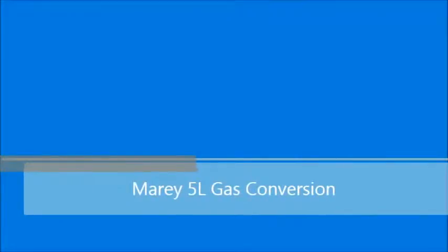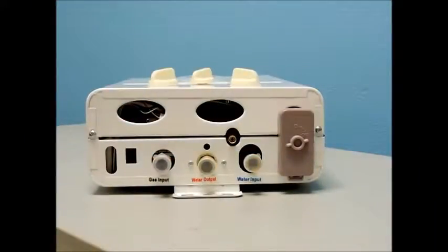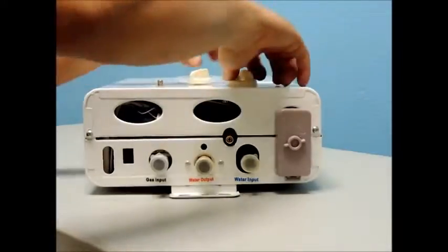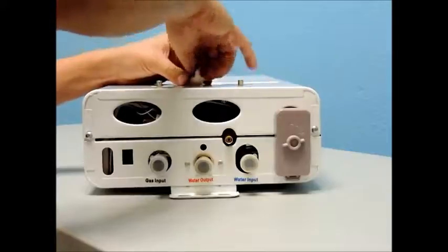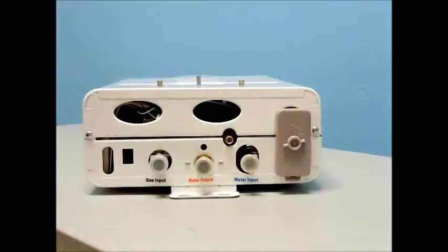This video will show you how to install a conversion kit, which will convert your unit from using one fuel type to another, i.e. changing it from propane to natural gas on your 5 liter Marey tankless water heater. It would be best to remove this unit from the wall and place it horizontally on a table or workbench and use an impact driver to remove all the screws in this process.